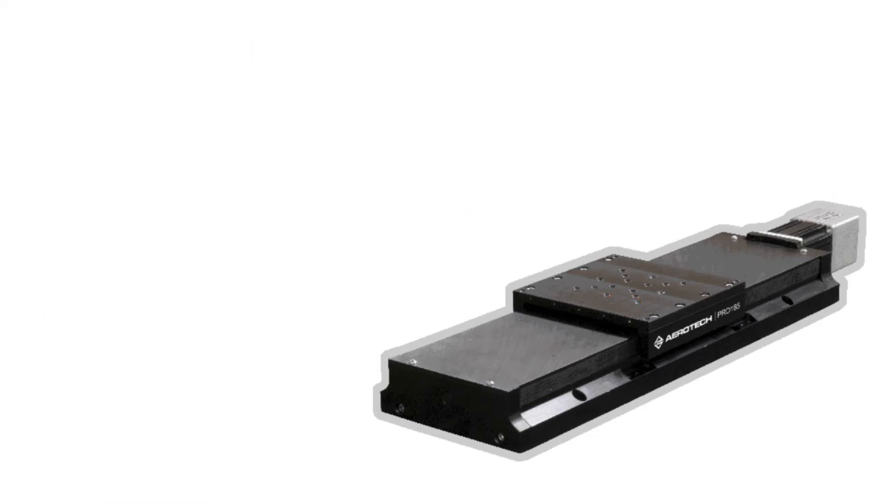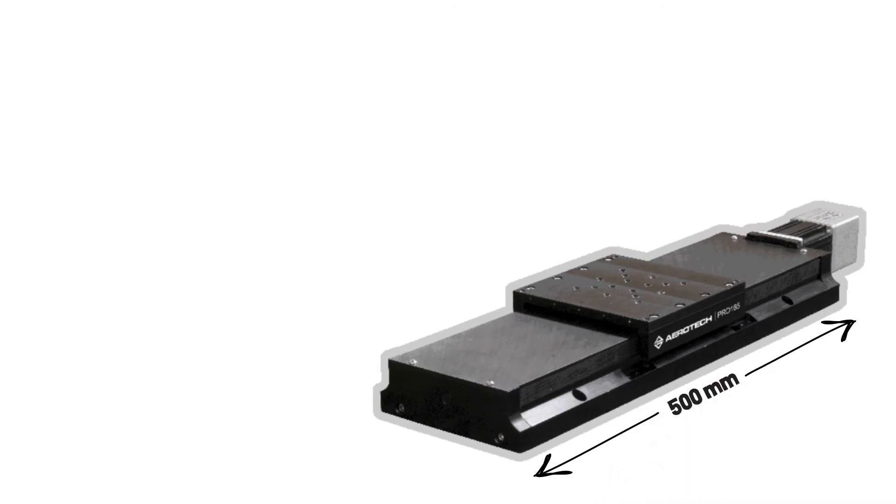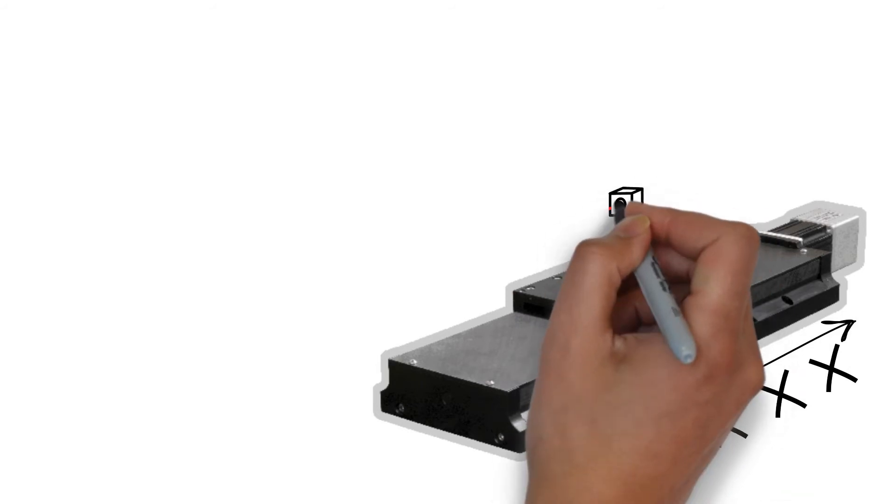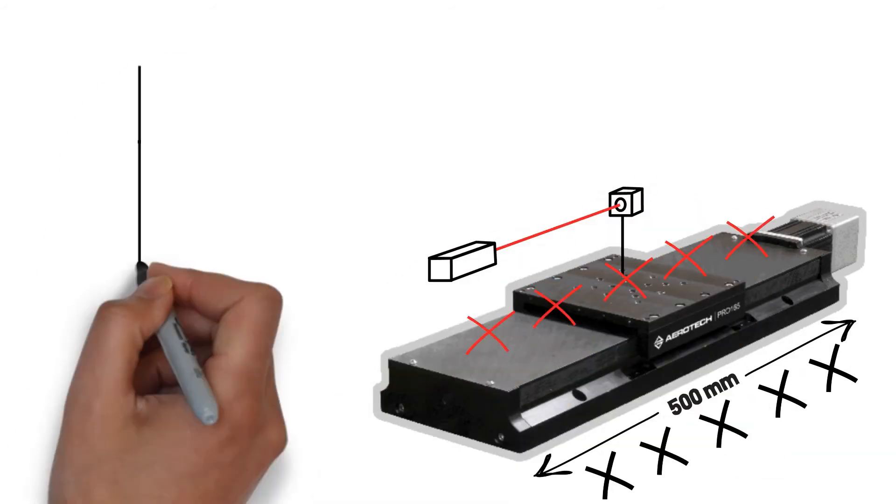Let's say that the stage has a travel range of 500 millimeters, and we want to calibrate the accuracy over the entire travel. We would move the stage to a range of positions and use the interferometer to take a measurement at each position.